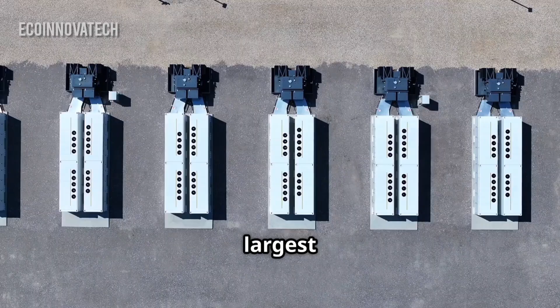Flow batteries, the marathon runner. While lithium-ion excels at rapid response, a different architecture is purpose-built for endurance, the flow battery. The most mature of these is the vanadium redox flow battery, or VRFB. Unlike conventional batteries where energy is stored in the electrodes, a flow battery stores energy in two large, external tanks of liquid electrolyte. To charge or discharge, these liquids are simply pumped through a central stack of electrochemical cells.